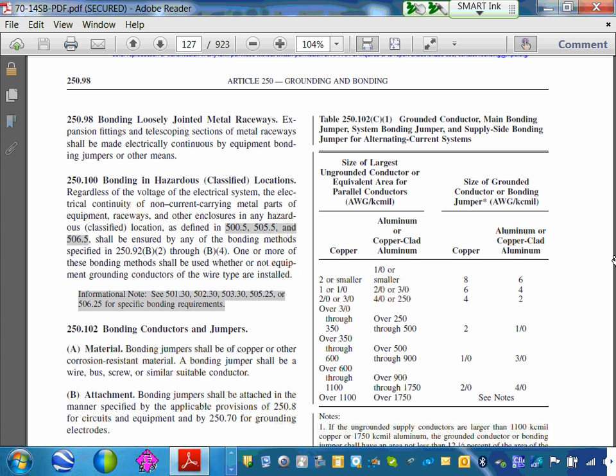Craig, my friend, in the NEC code book, there's so many formulas, so many calculations. That's why I give you guys the reference. That's on the test. Because you're gonna get confused. That's where you take the references and you have basically everything that we do. Write yourself a note. When you size a neutral, go to this and do this. When you derate for the receptacle, go to this and do this. And you bring it with you. Otherwise, I dare anybody to remember all this stuff. Unless you're a goofy like Chad that's been using it for 20 some years.